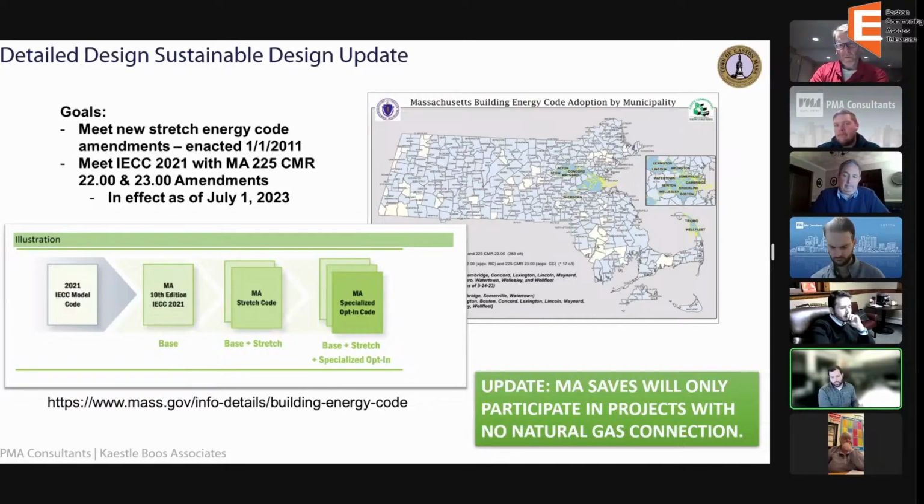For the project as we presented it previously, the major things that we were doing with natural gas were domestic hot water, which is a fairly small load, and cooking appliances throughout the building, which in terms of monetary impact is essentially nothing. It's more of what people prefer. In those cases, we will likely go to induction ranges. It's usually the range that's the issue.